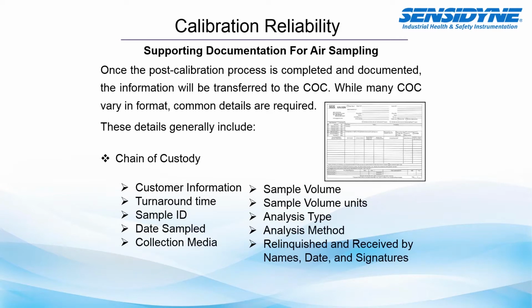Now that supporting documentation, once your post-calibration process is completed and documented, will be transferred to your chain of custody. While many chain of custodies vary in format, common details are required. These details generally include your customer information, your turnaround time, your sample ID, your date sampled, your collection media, your sample volume units, your analysis type, your analysis method, and then your relinquished and received by information. Note that a lot of these pieces that go onto your chain of custody should align with your calibration log as well as your field notes.